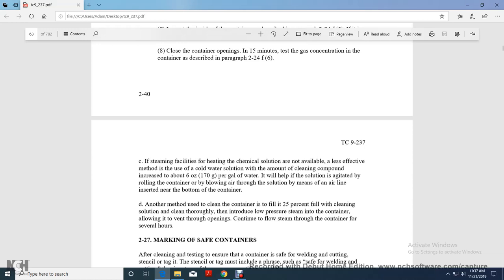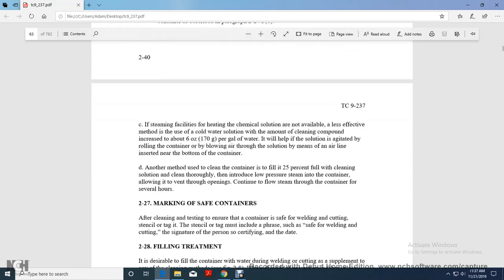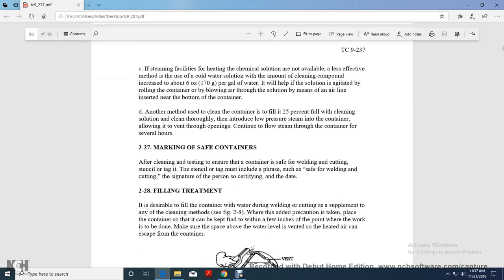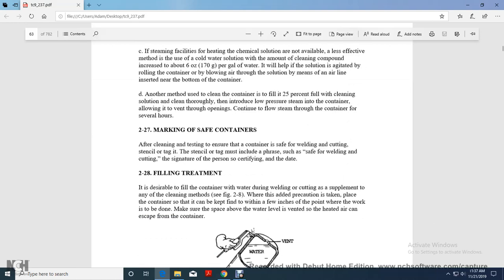If the steam facility for heating the chemical solution is not available, use the cold water solution method, which is less effective, with the amount of cleaning compound increased to about 6 ounces per gallon of water. Help the solution agitate by rolling the container or by blowing air through the solution with an air line inserted near the bottom of the container. Another method is to fill the container 25% with the cleaning solution, then introduce low pressure steam into the container, allowing it to vent through the openings, and continue the slow steaming of the container for several hours.